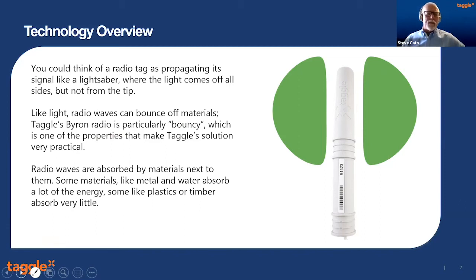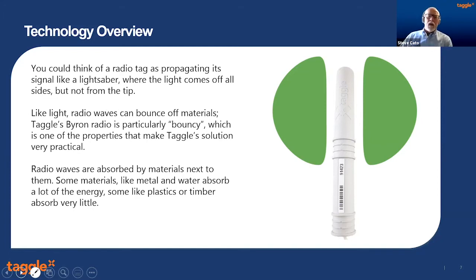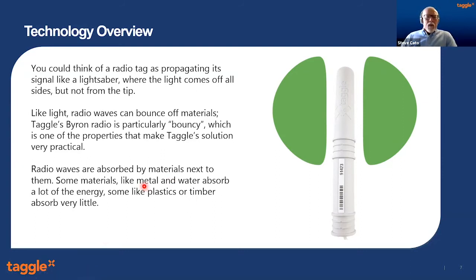Radio waves are absorbed by materials next to them. Things like metal and water absorb lots of the energy. We're talking about low energy devices here: 25 milliwatts for our low power tags and 500 milliwatts for our high power tags. Your mobile phone is one watt, so we're not even as powerful as a mobile phone. We want to avoid things like metal and water. Plastics and timber absorb very little, although wet timber and wet plastics are not so good.